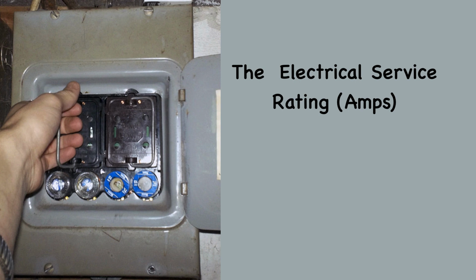Circuit breaker panel: since the early 1960s, homes have generally been wired with circuit breaker panels. This type of panel provides both 120 and 240 volts of power. Early services may provide 60 amps of power, while large houses built today may have 200 amps or more of power. Homes with 60-amp or 100-amp service often require an electrical service update during major remodeling or expansion projects.